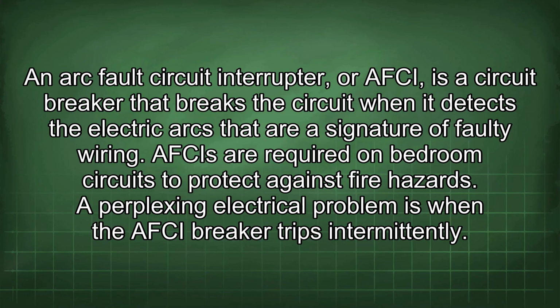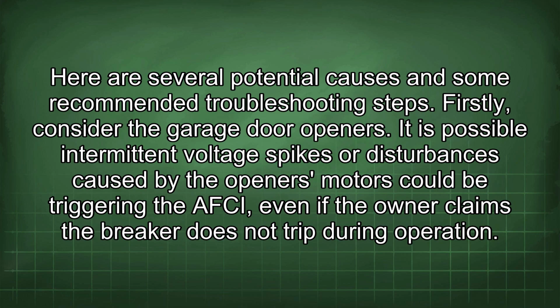An arc fault circuit interrupter, or AFCI, is a circuit breaker that breaks the circuit when it detects the electric arcs that are a signature of faulty wiring. AFCIs are required on bedroom circuits to protect against fire hazards. A perplexing electrical problem is when the AFCI breaker trips intermittently. Here are several potential causes and some recommended troubleshooting steps.